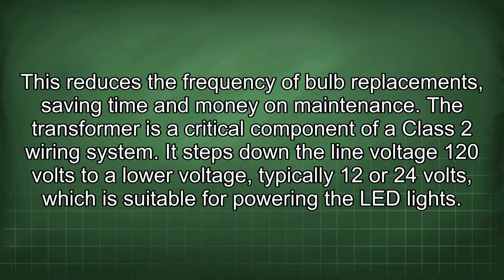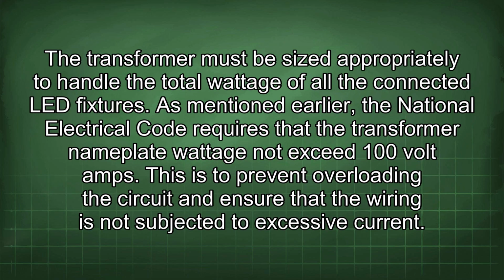The transformer is a critical component of a Class 2 wiring system. It steps down the line voltage of 120 volts to a lower voltage, typically 12 or 24 volts, which is suitable for powering the LED lights. The transformer must be sized appropriately to handle the total wattage of all the connected LED fixtures. As mentioned earlier, the National Electrical Code requires that the transformer nameplate wattage not exceed 100 volt-amps. This is to prevent overloading the circuit and ensure that the wiring is not subjected to excessive current.